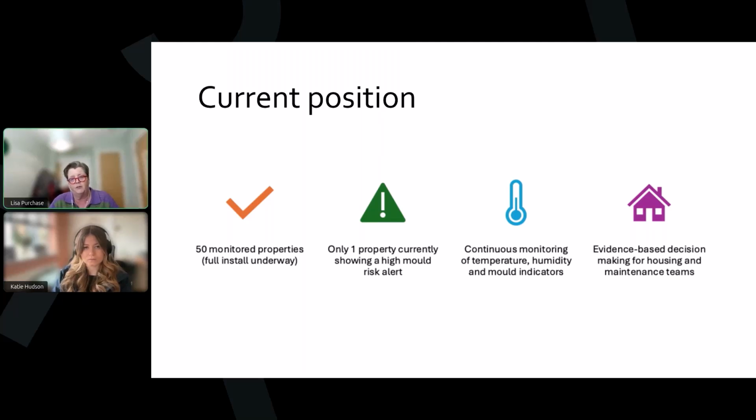One of the things that we found during our trial period, or through our initial 20% period, was that when we were having the gas boilers serviced in particular, the Switchee devices, there's one placed on the boiler and one that connects to the thermostat, they'd lose connection because the boiler had been turned off for various different reasons. And so the boiler had been serviced and we got a new gas safe certificate, but the Switchee device had lost connection through to the dashboard and through to the monitoring. We'd identified this early on as a problem, and we'd sent out engineers a couple of times to reconnect them, but that's quite expensive to do.